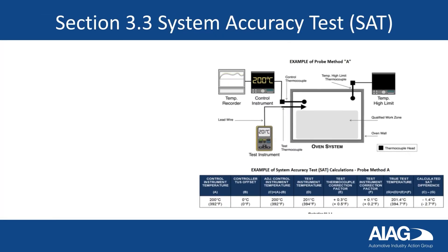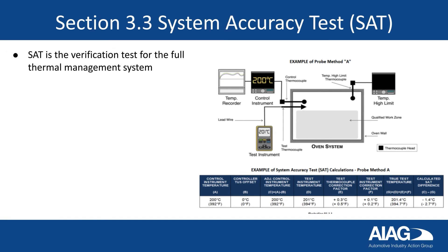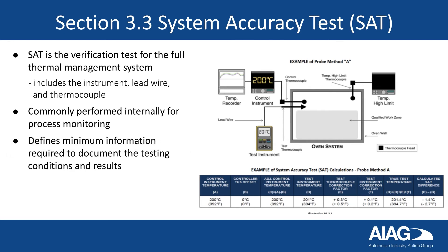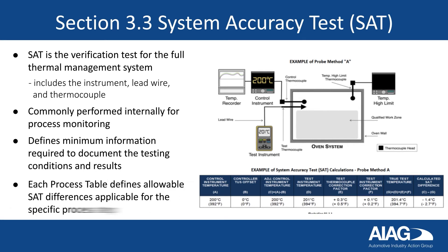Section 3.3 covers the system accuracy test, which verifies the full thermal management system, including the instrument, lead wire, and thermocouple. The SAT is commonly performed internally for process monitoring. It defines the minimum information required to document the testing conditions and results. Each process table defines allowable SAT differences applicable for the specific process step.